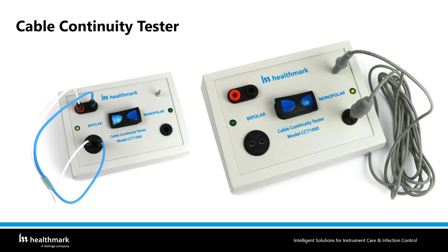So biomed can help. The other area where, as a biomed, we didn't get involved is the inspection of those insulated instruments. Anytime energy from the ESU goes to any of these cautery instruments, monopolar or bipolar, the shaft is supposed to be coated, and you want the energy to go to the tip. And during the operation, the surgeon does not see this part because the light is shining on this area, and the surgeon performs the surgery based on that.